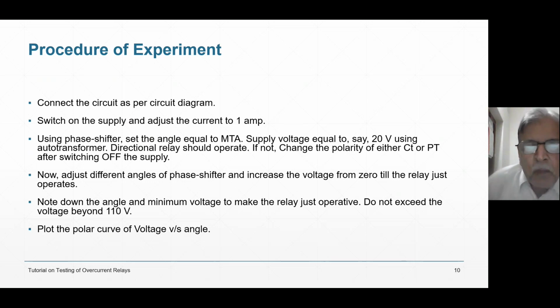Directional relay must operate at maximum torque angle. Directional relay must operate, but it is quite possible that your CT PT polarity is wrong, and rather than in the operating region, you are in the blocking region. Therefore, if so happens, you will have to change the polarity either of the CT or PT. मतलब बदल दो, direction बदल दो, change the polarity of CT or PT. Now the relay will operate. Okay, done. Now what do you do?